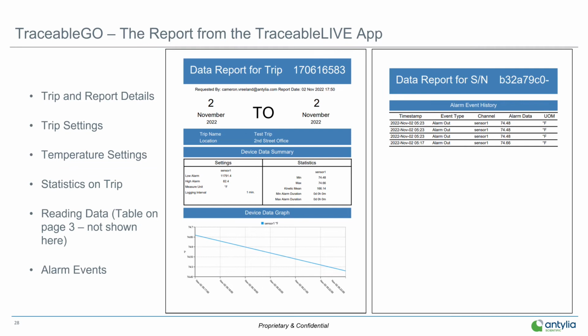TraceableLIVE also has analytics built in, so it runs statistics on your trip. This trip was only about 20 seconds long since I was just generating a report, so my kinetic mean is a little funky, but it'll calculate it for you anyway. It also gives you the device data graph, the readings table on the third page which I didn't pull up here, and your alarm event history.